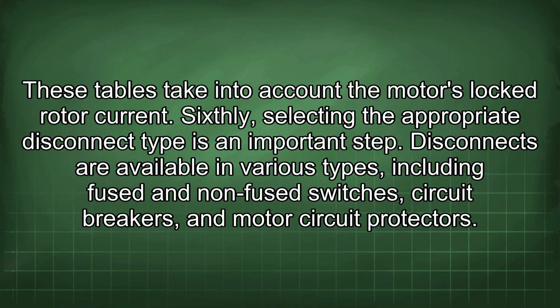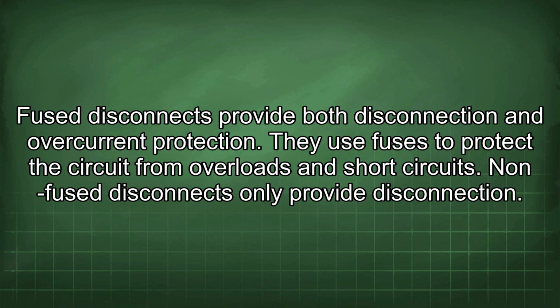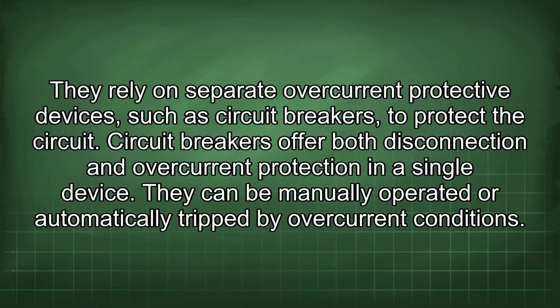Sixthly, selecting the appropriate disconnect type is an important step. Disconnects are available in various types, including fused and non-fused switches, circuit breakers, and motor circuit protectors. Fused disconnects provide both disconnection and overcurrent protection. They use fuses to protect the circuit from overloads and short circuits. Non-fused disconnects only provide disconnection. They rely on separate overcurrent protective devices, such as circuit breakers, to protect the circuit.